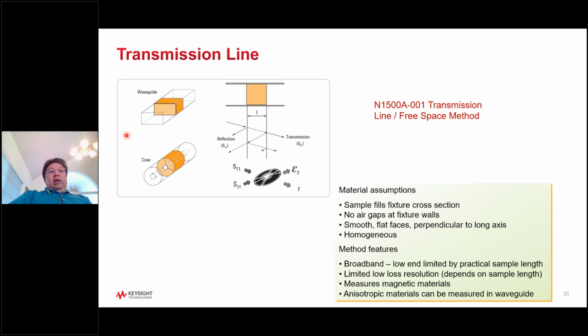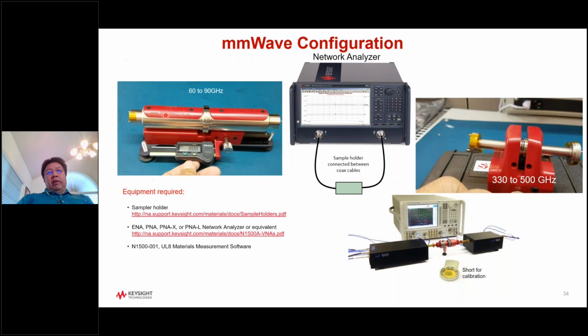So how it works, as mentioned, you require all 4 S parameters, and Keysight software option 001 transmission line method, and there are some measurement sample restrictions, such as no air gap. Our software actually, without going into details, if you have an air gap, meaning your sample is not tightly fit, we have some way to correct the air gap as well. So if you need to know more detail, we can discuss.